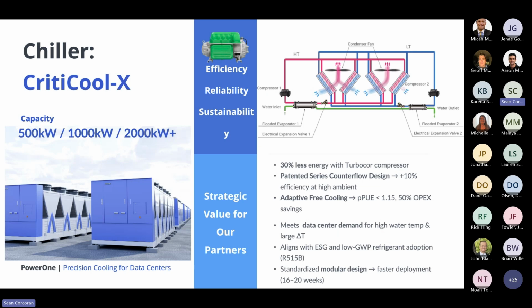Our chiller, anything from 500 kW to 2 megawatts. We have 30% less energy with our Turbocor compressor. We have something called our patented series counterflow design, which is basically when you have a chiller that has a dual refrigerant circuit working in series to achieve higher water temperature and delta T, it usually creates a problem on the other side due to the imbalance in compression ratio. So when the evaporators work in series, the low temperature circuit will carry that extra weight at the condenser side. Since the condensers are breathing the same hot air, this will result in a 30% compression ratio increase on the low temperature circuit side, which will cause low efficiencies.